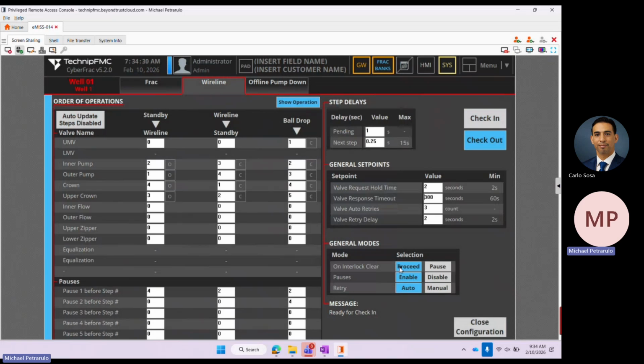General modes, this section is actually pretty helpful. If you are going through a sequence and an interlock pops up saying, for example, you have to equalize this valve, as soon as you equalize it, the way it's set up here, it'll proceed immediately. It's not going to wait for you to hit resume. This is helpful for things like CP Simul, where if they hit an interlock mid-transition and equalize it, the system will auto proceed and they don't have to jump to other pages to keep things rolling. If you have it set to pause, it'll pause immediately on interlock, and once the interlock clears, you have to physically hit resume.